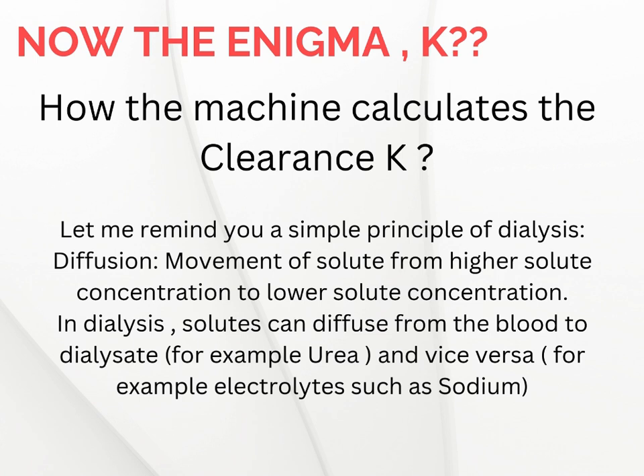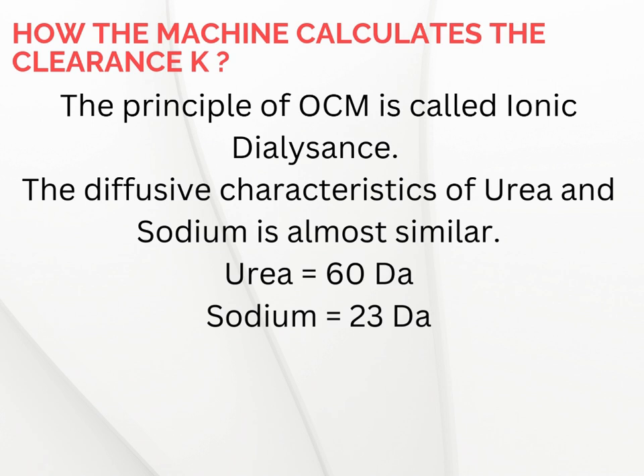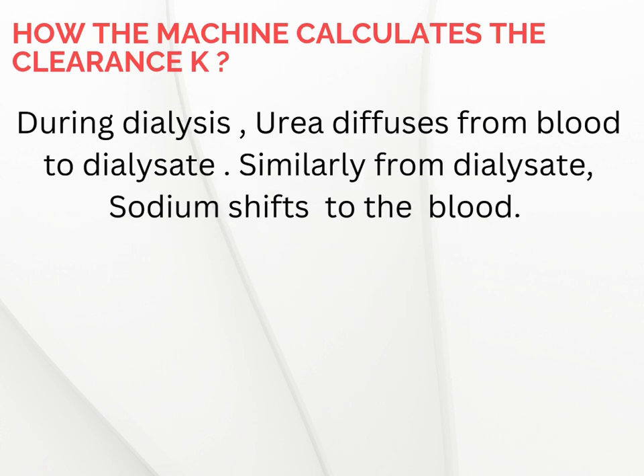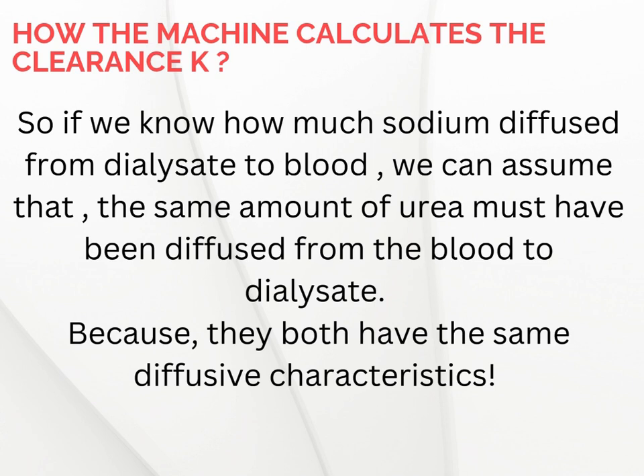How does the machine measure clearance without a blood test? It uses an innovative principle called Ionic Dialysance. Urea and sodium have similar diffusive properties, so by tracking how much sodium moves across the membrane, the machine estimates how much urea is removed. The machine has two conductivity sensors — one at the dialysate inlet and one at the dialysate outlet. The machine momentarily increases sodium levels and continuously monitors how much gets transferred. If sodium shifts, urea must have shifted too.